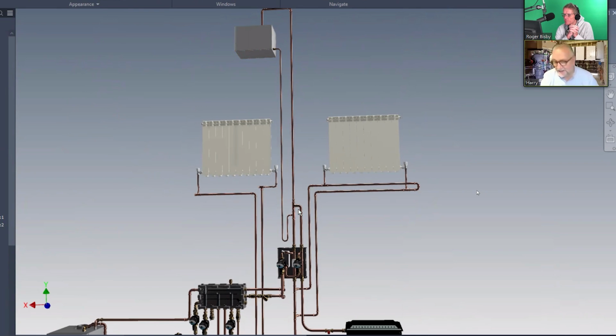The harm is that, just as I said to you, hot water wants to rise from the solid fuel boiler. Hot water wants to rise from the cold feed if it's connected to a hot pipe. It rises up the cold feed, goes in, and it's stored volume in the tank. That tank water is hotter than the air in the attic. It evaporates. The boiler lets fresh water in, and now you've got a stream of fresh water going into your heating system. Got it. It's the evaporation.